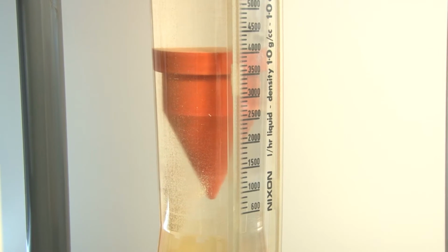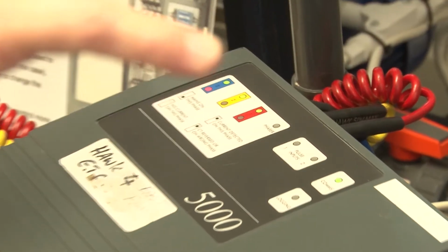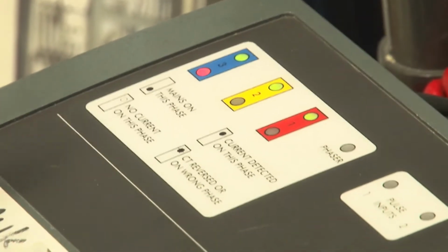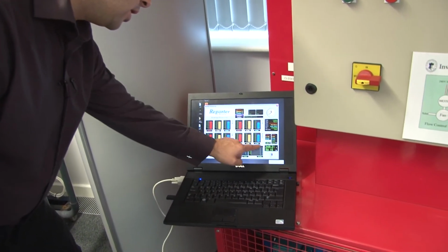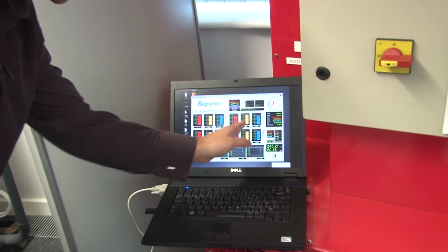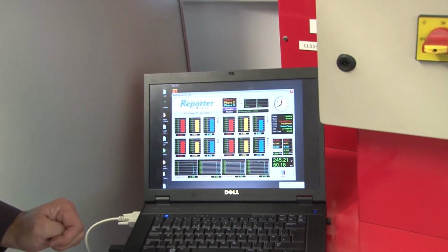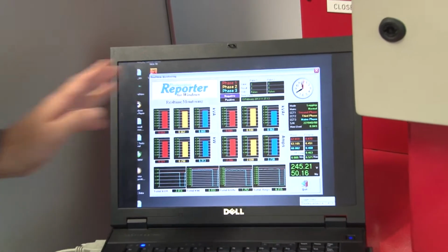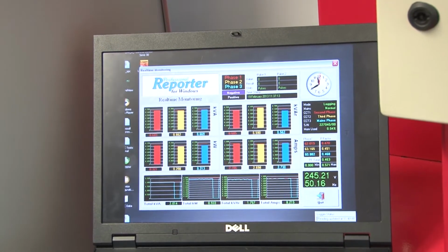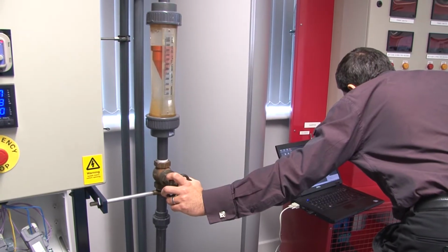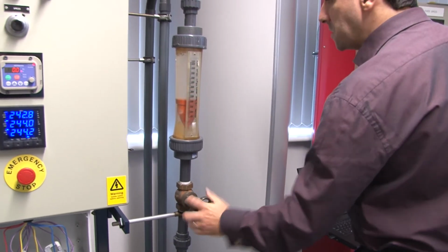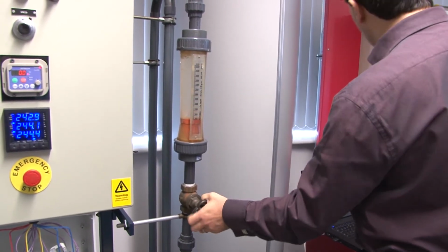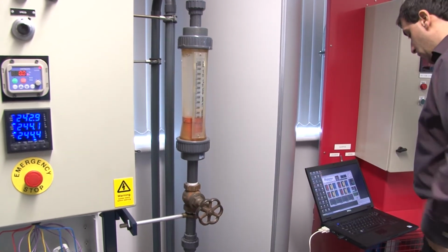So we're measuring the amps that are actually pulled by the motor. That's what the CTs, or current transformers, are measuring on each of the three phases. The other thing that we are measuring here is the voltage of one of the phases, in that instance the blue phase. So we have the voltage of this blue phase, and how much amperage it's actually pulling.